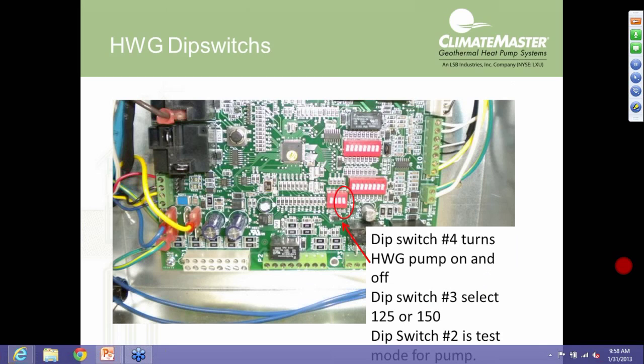And then number 2 is a test mode for the hot water generator pump. What that does, as long as the unit is powered and the compressor contactor is pulled in, we can run the pump, and it'll run for 5 minutes regardless of what the thermistor readings are that are controlling the hot water generator. And that will allow you, especially on a startup, to make sure that we've got all the air out of the system, we've properly bled the piping between the heat pump and our hot water tank, so that we know we're not going to be burning up that little Taco circulating pump inside there. So that's a nice option.